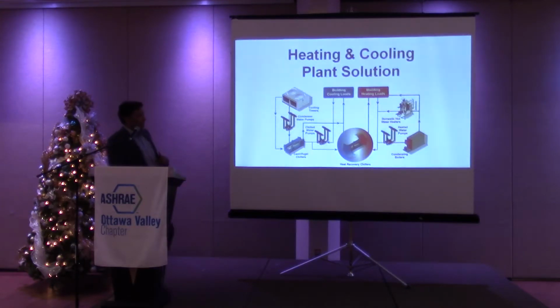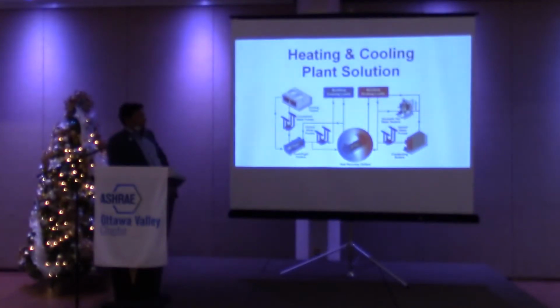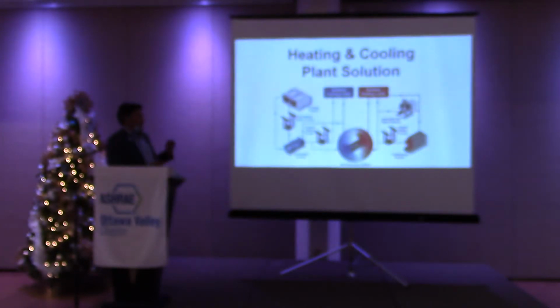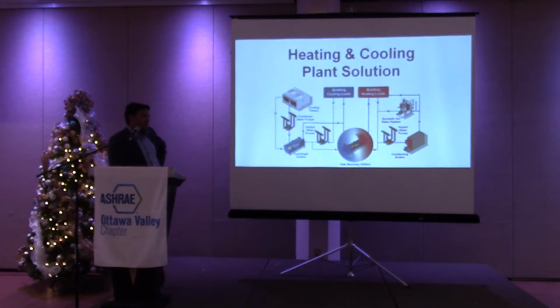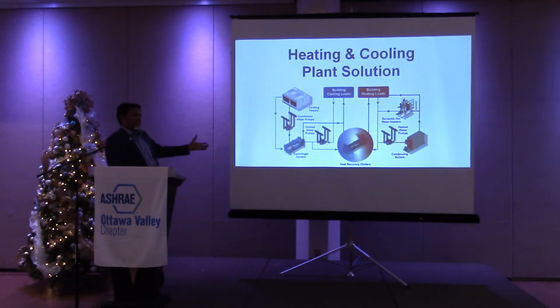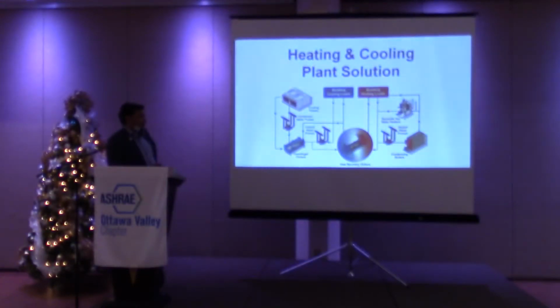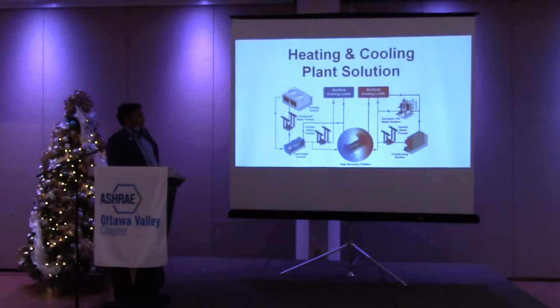So what that allowed us to do with the low return water temperature was to drive our condensing boilers and make sure we can maximize the condensing efficiency, the boiler efficiency for the plant. We also included the domestic hot water system in this hydronic heating plant. And the reason we did that was instead of using steam, that's very traditional in healthcare facilities to generate domestic hot water, we decided to do it with the hydronic system because we could use the cold water to pre-cool the return water temperature to the condensing boilers, and again make sure that we had low return water temperatures going to those boilers, maximizing efficiency.